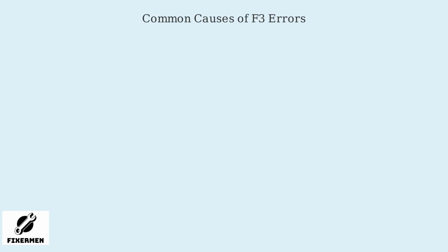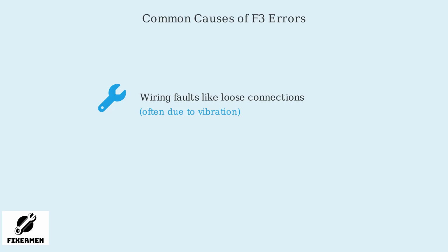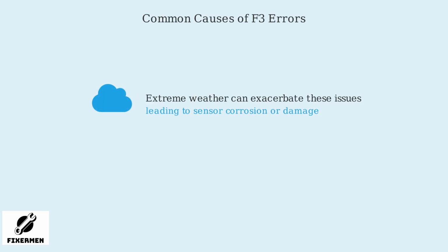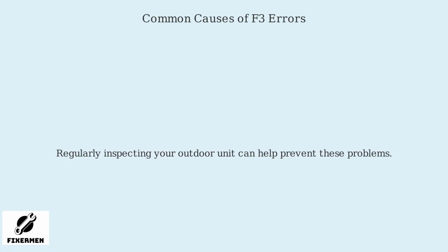Several factors can trigger an F3 error in Carrier HVAC systems. These include wiring faults like loose connections, often due to vibration, sensor degradation from moisture or ice, rodent damage to the wiring, or electrical surges. Extreme weather can exacerbate these issues, leading to sensor corrosion or damage. Regularly inspecting your outdoor unit can help prevent these problems.